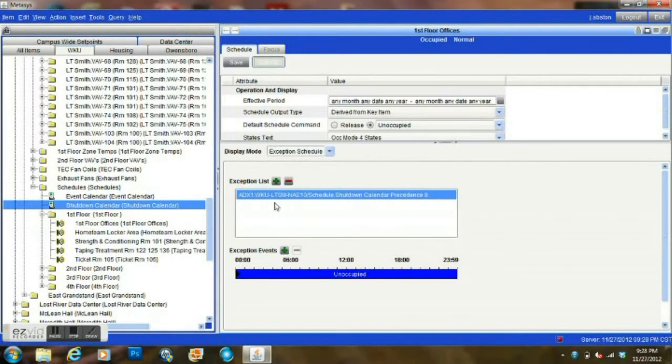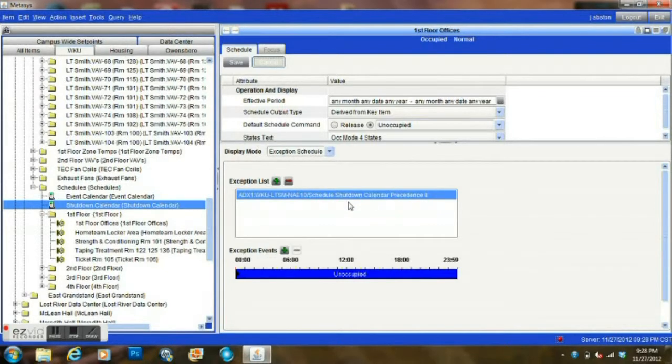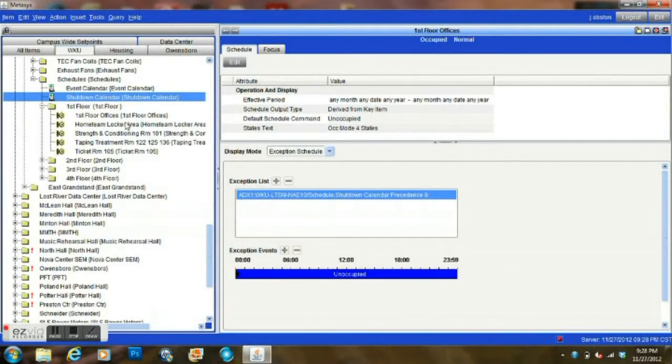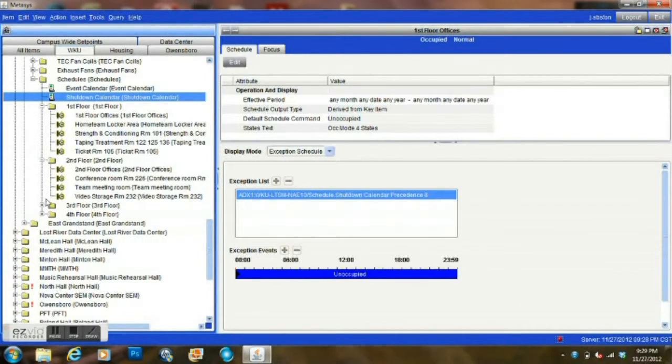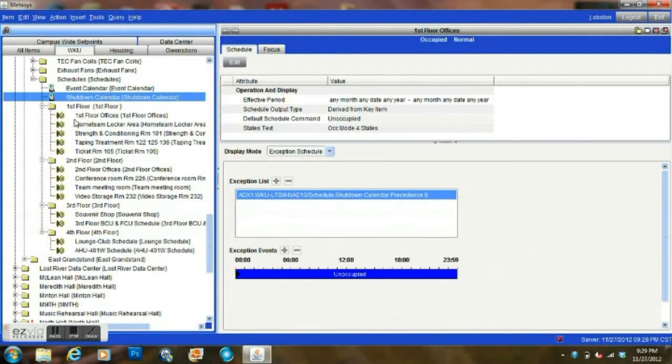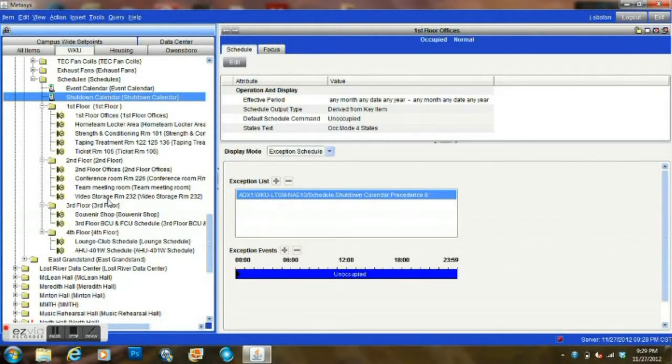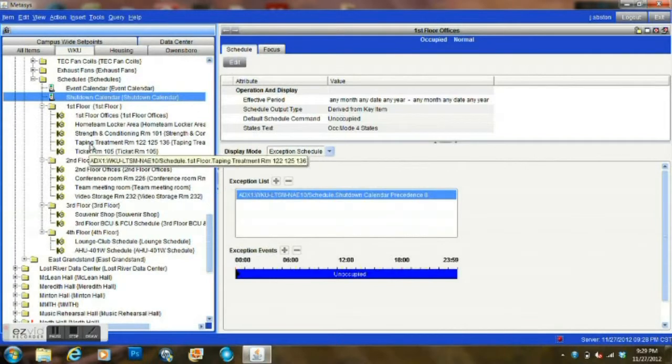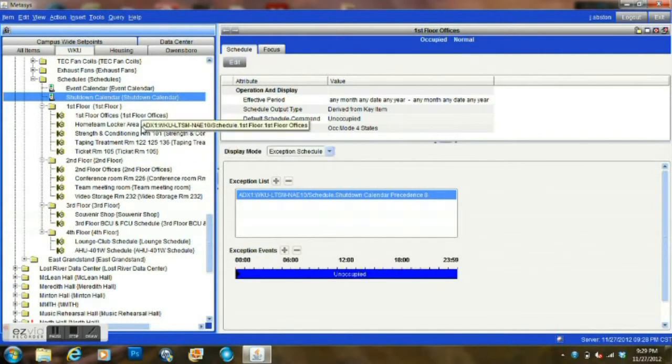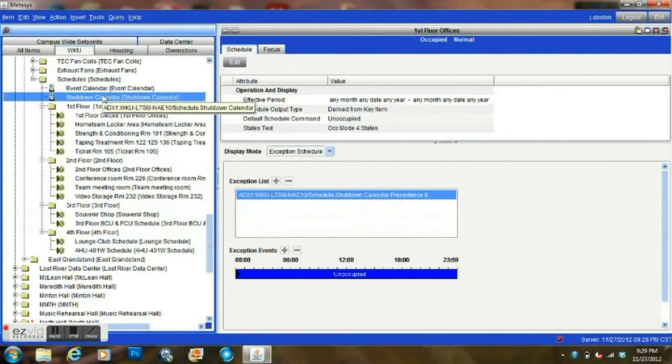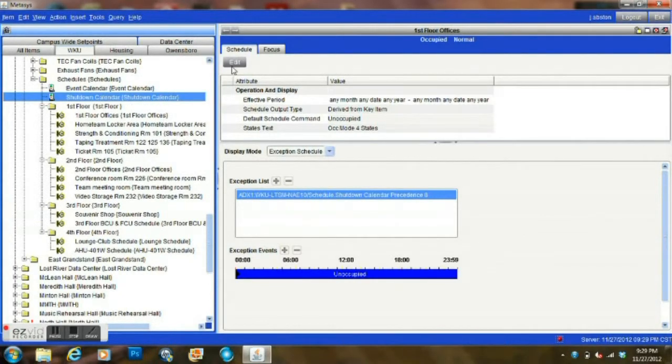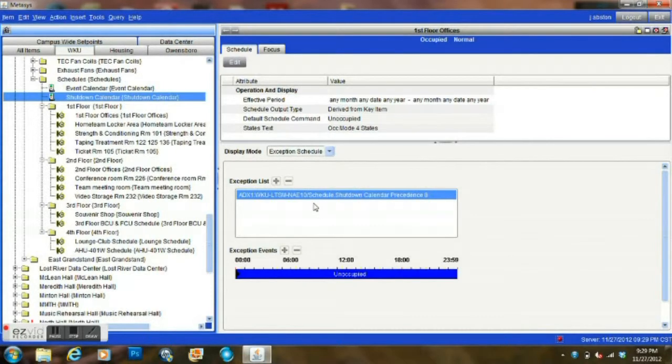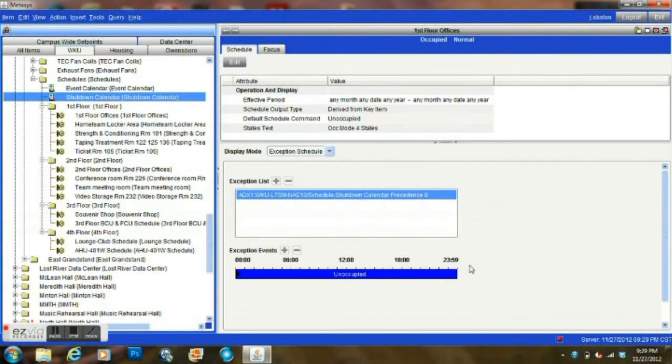Now then, by tying this schedule to a calendar, what we can do is really simplify a lot of things. The holiday shutdown calendar is going to be the example, because instead of having to go into each one of these schedules and set up a date where they are going to be off, like during our holidays when nothing is running, we simply tie each of these schedules to this calendar. And then when it is tied to that particular calendar, we set up a time for that calendar, for that particular schedule to be unoccupied for that entire day.